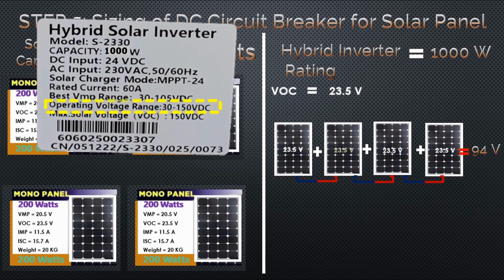Since we decided to use 4 panels in series, the next thing to do is to look for the short circuit current or ISC of the panels, because that will be your reference in sizing the DC circuit breaker. If we look at the nameplate of the solar panel, it has a short circuit current of 15.7 amperes per panel. Since the 4 panels are in series connection, the current flowing in the circuit is the same at 15.7 amperes.